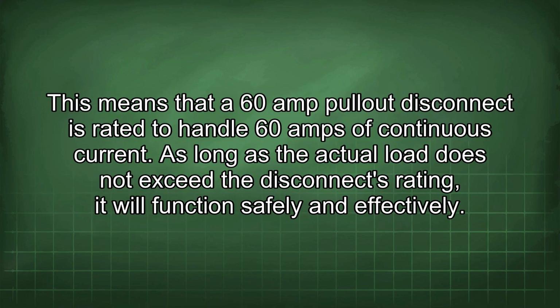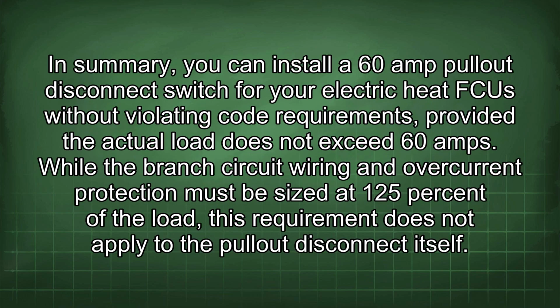This means that a 60 amp pull-out disconnect is rated to handle 60 amps of continuous current. As long as the actual load does not exceed the disconnect's rating, it will function safely and effectively. In summary, you can install a 60 amp pull-out disconnect switch for your electric heat FCU without violating code requirements, provided the actual load does not exceed 60 amps.